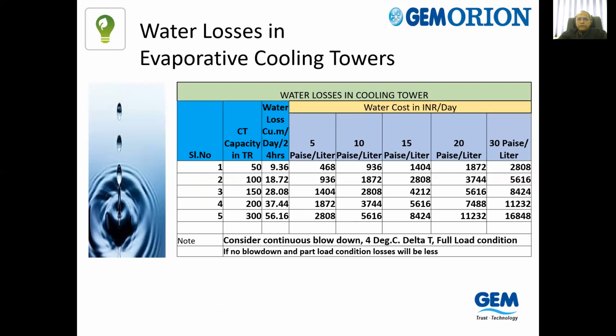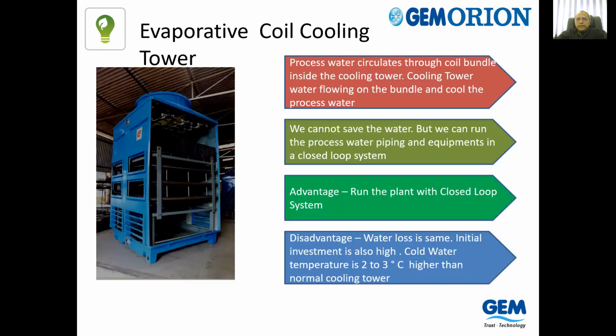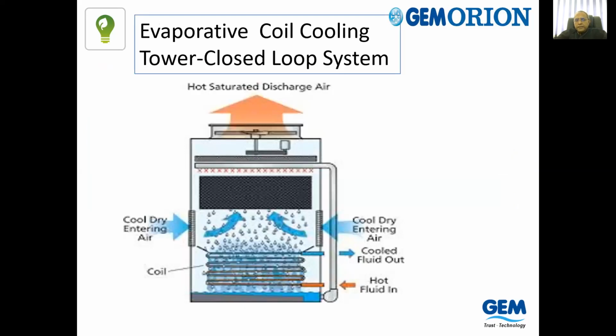And because of the evaporation losses, roughly about 1% of the water will continuously evaporate. So people have to arrange for the water. We know the situation faced a couple of years back with water scarcity. So people are now looking at solutions so that they can run the entire plant lifetime without consuming even one drop of water. So we have the evaporative coil cooling tower also, which is one of the processes wherein the heat exchanger can be put inside the cooling tower and then used for indirect cooling.